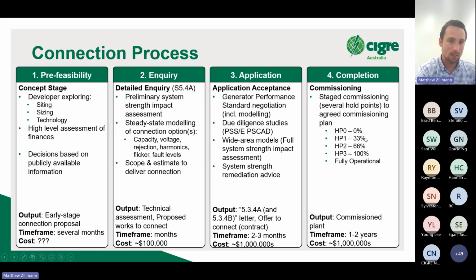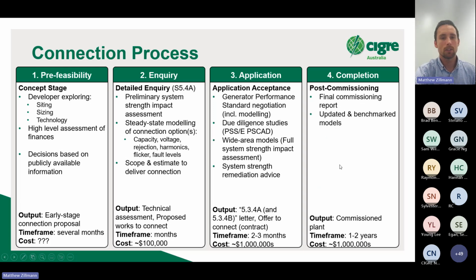They then have to provide technical reports demonstrating their system operated as expected over that period. While that report is being reviewed, they're run back to the previous hold point. Going through these stages can take quite a while, which for a generator that's invested a lot of money is definitely something they don't want to drag on, since they're effectively constrained to partial operation. By the time they reach full operation, they then have to close out their commissioning.